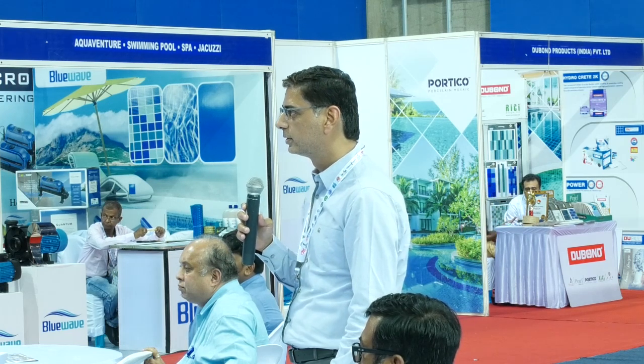Very true, very true. First of all, connecting the drain of a pool to the sewer system or stormwater system is incorrect. Stormwater and sewer systems are not designed to take the load. When you drain a pool, it is like 1 lakh liters of water coming out within half an hour or an hour. So never connect. Secondly, connecting it to drainage lines is very dangerous because cross contamination may happen. We generally do it through the filtration pump only.